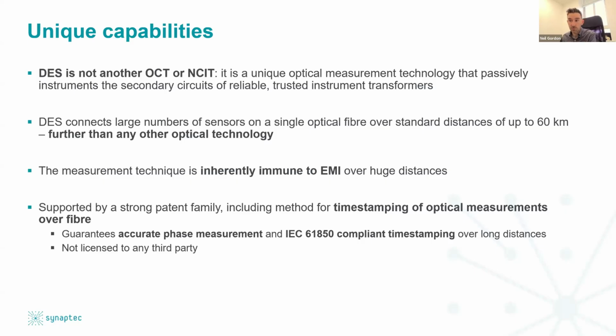And crucially, our methods are protected by a strong patent family. And there's one in particular that I just want to flag, which protects our method of time stamping those measurements which are taken over that very wide area. So any system that deploys passive optical sensors over fiber, be that DES or OCTs or NCITs, will naturally incur a time delay as the light traverses that fiber over tens of kilometers. What our patent does is it accurately corrects for that time delay.